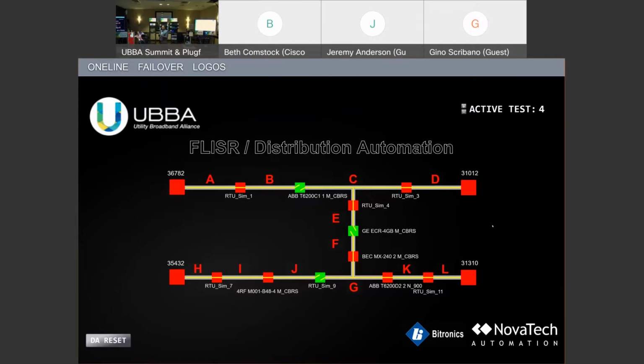And then some of those, a small portion of those, have been automated. And even when you see the sectionalizing diagram, this can be 100 miles of power lines. Between each of these automatically controlled points, there might be 5 or 10 more manually controlled sectionalizing points. So the same thing that we're automatically doing here would be manually done in the field for a technician to even isolate the problem down to just a block or even a customer, depending on where the actual issue is. They'll try to isolate it down as small as possible when they arrive on scene.